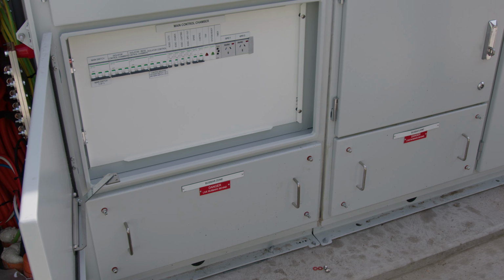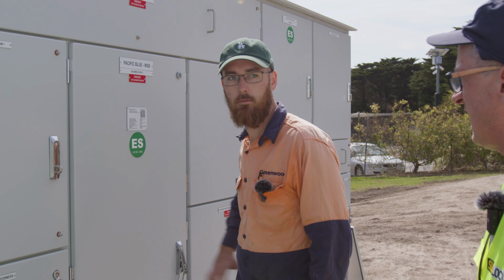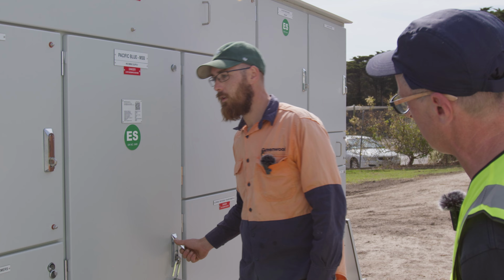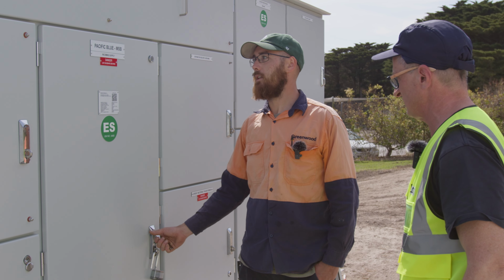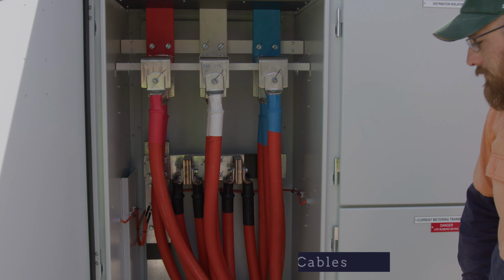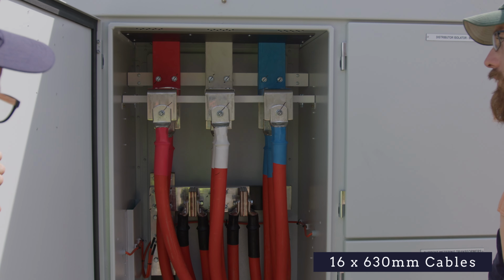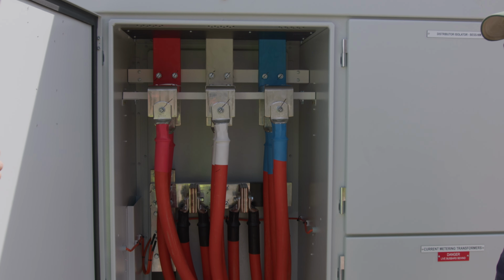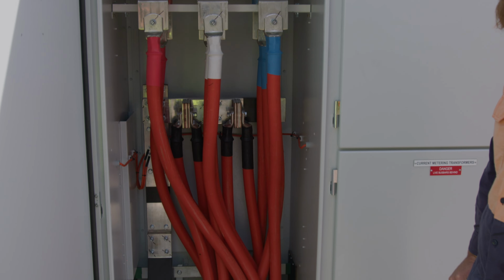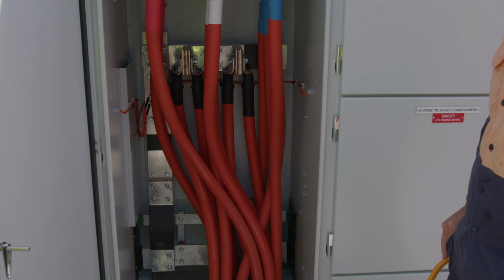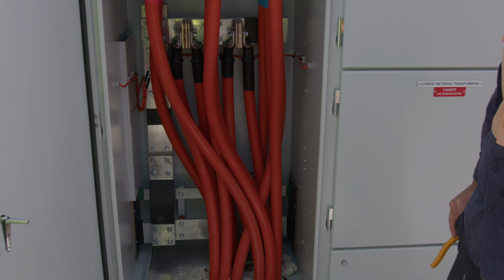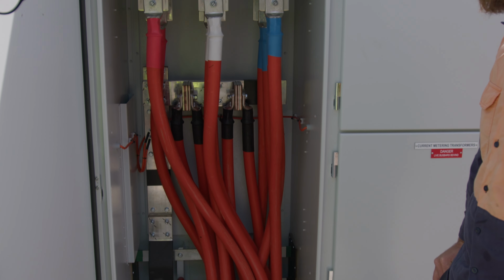But let's talk about this large cabinet here. What's going on? What's behind there? This large cabinet is our incoming supply, so it has 16 630mm cables. They're sort of the biggest really that are around, or do you get bigger cables? You can get larger, but the regulation books don't have much information on them, so you have to go off the manufacturer's specs for anything larger than that.